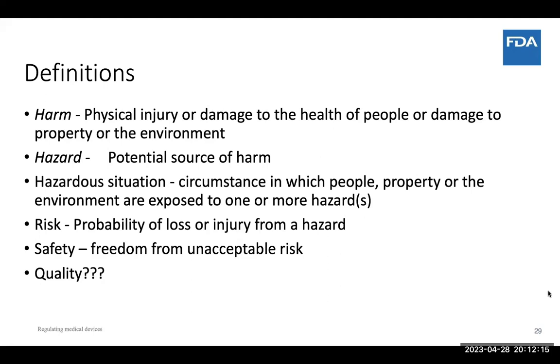Safety is freedom from unacceptable risk. Anything you do in medicine, there is some risk, so you cannot avoid some risk. But the question that FDA tries to debate with the manufacturer is the risk versus the benefit of that procedure or device. Can it be minimized? Has the manufacturer done every effort to minimize it? And at the end, is it acceptable versus the benefit it has?